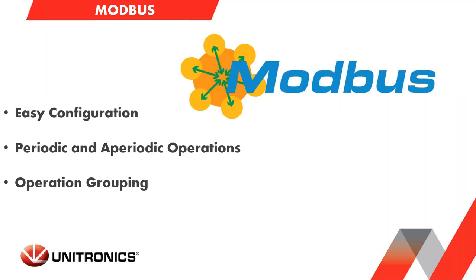Modbus is one of the most common protocols being used today. It's an industry standard. We can communicate via both RTU and TCP networks, created with a client-server dynamic. The client device sends both data and requests to the connected servers. The UniStream can act as both the client and server. Communication is easily configured in the project rather than programmed.